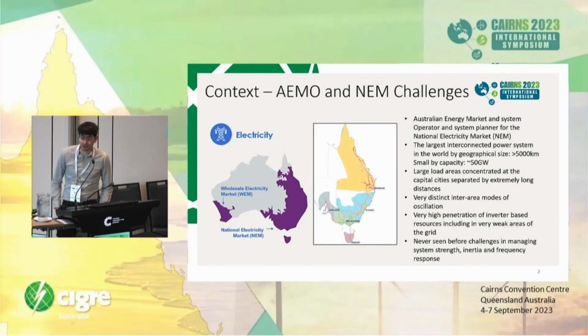But despite that massive size, it's quite a small capacity, only about a 50 gigawatt system, which gives us a lot of unique challenges that aren't really seen many places else around the world, particularly very distinct inter-area modes of oscillation. So our system is actually unstable without active damping for those inter-area modes. We've got a very high penetration of inverter-based resources, particularly in very weak areas of the grid. And we're seeing many never-seen-before challenges, such as issues with low system strength and low inertia, that are really challenging the way we have to manage and operate the grid.